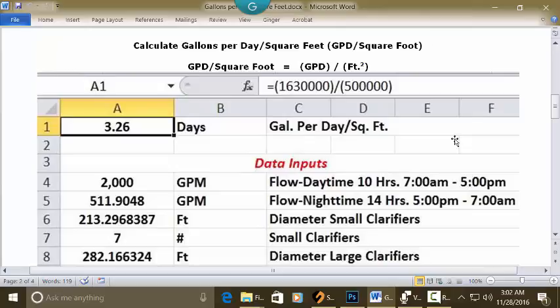Put your cursor in C1 and type 'gallons per day per square foot.' Your answer is going to be in days. Put your cursor in A1, make it numbers with two decimals, bold and centered, and in the address bar type this formula: equal sign, open parenthesis, 1,630,000, close parenthesis, division key, open parenthesis, 500,000, close parenthesis, and press Enter. In A1 your answer is 3.26 days, based on this current flow and the clarifiers in service.